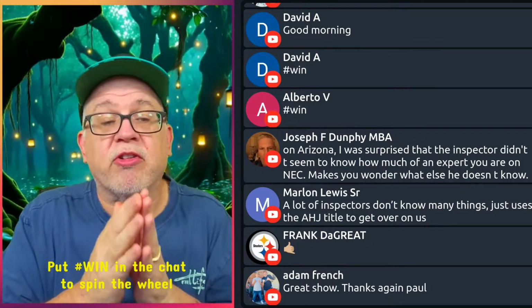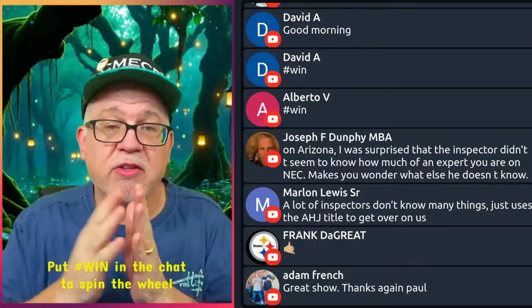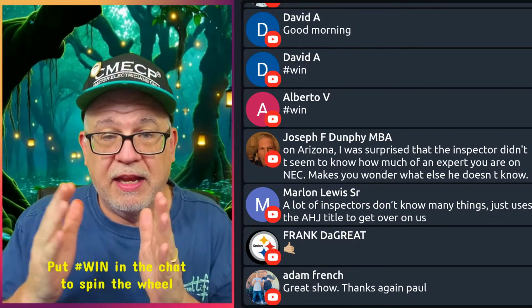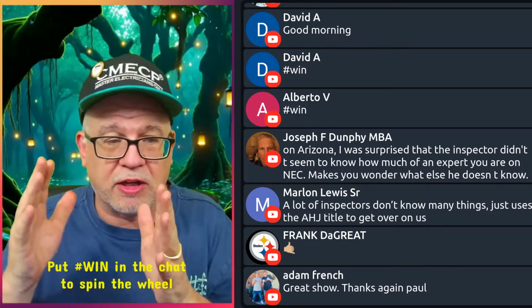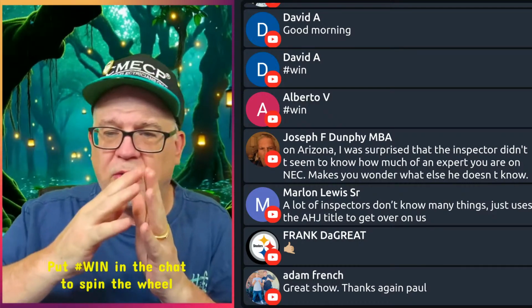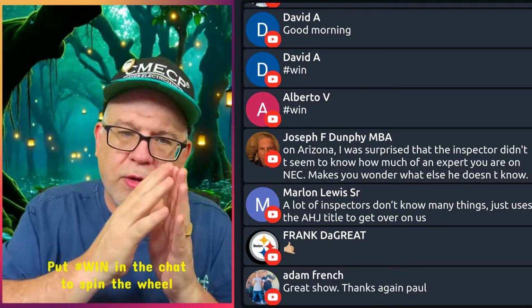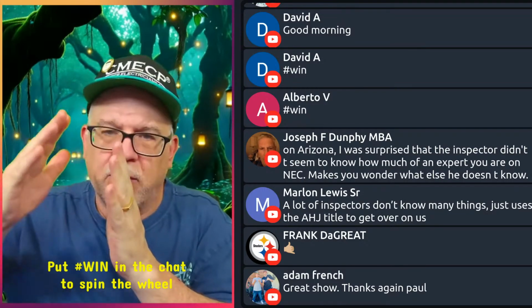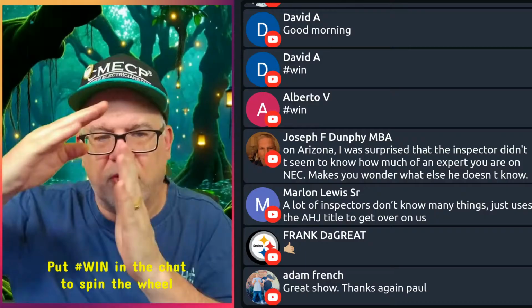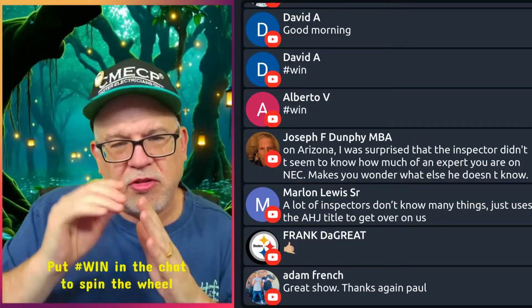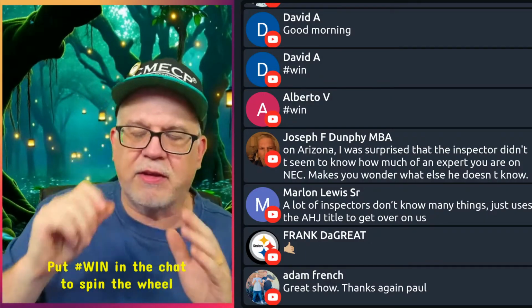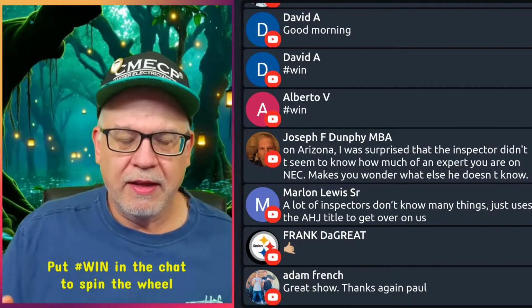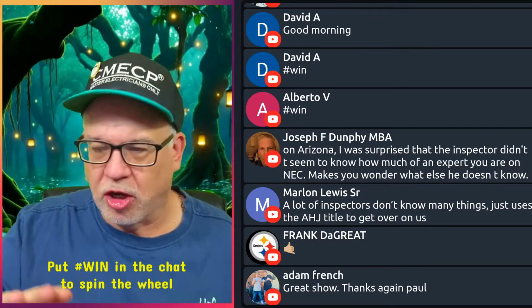That is why breakers come in different trip curves, because there are applications where there is a delay, and that's where we start looking at selective coordination and when something trips. We don't want it to trip too soon because we understand that it could get into this area, and we don't want it to trip until it gets here. So you start looking at these curves and make sure you fall nicely in there, you know, that type of thing. You know what I'm saying? So at the end of the day, follow the nameplate. It's going to be fine.